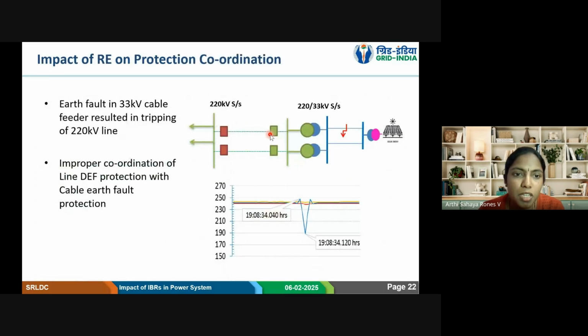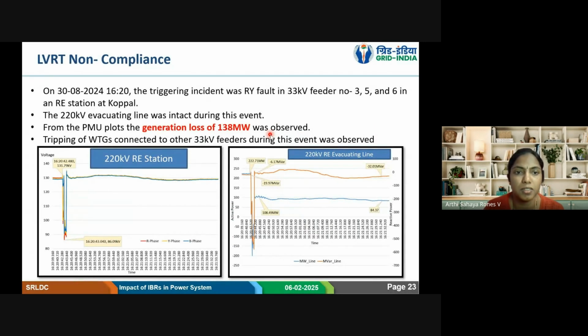So next, I want to share a few things regarding the LVRT non-compliance issues. So now we saw mostly the grid side faults and grid side protection systems. So I would like to next touch upon grid side fault and how the inverters have behaved. So that is where we talk about the LVRT and HVRT compliances and all. So in the previous session also, the speaker was explaining about those testing and all. So before any model gets connected to the grid, we collect the testing of the model and we check whether it is proper or not. Then only the connectivity and all is given.